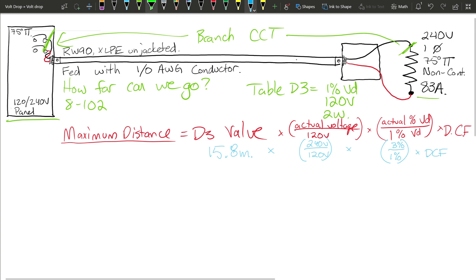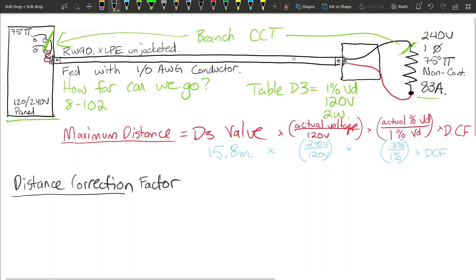Now let's talk about the Distance Correction Factor. According to the notes in Table D3, all the tabulated data is based on the conductor being held at essentially 60 degrees Celsius. Note 3 in Table D3 references the percentage of allowable ampacity. We have an 83 amp load supplied by a 1-aught conductor, which is rated for much more than 83 amps, so we can actually squeeze a little extra distance out of this conductor.